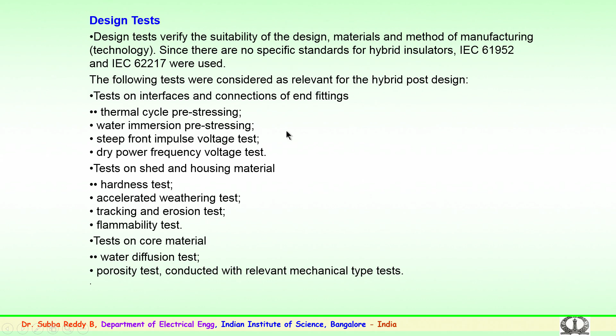The mechanical test: here the ceramic core of a hybrid post bears the mechanical load. This is transmitted to the core by the end fittings. Since, as mentioned earlier, no existing hybrid insulator standard is available for testing the mechanical properties, the reference is made to the IEC 60168 standard, which is being used. Similarly, for electrical type tests, the standard electrical properties in accordance with IEC 60168 are being followed for all the electrical type tests on these hybrid insulators.